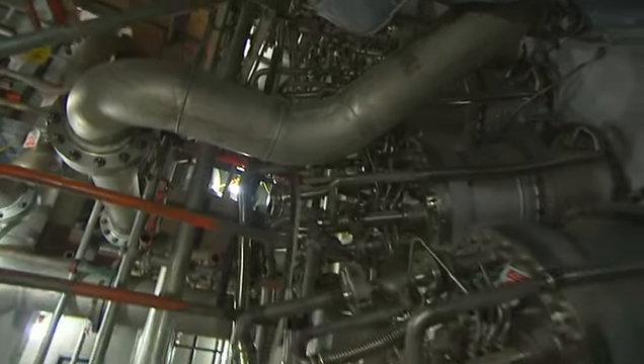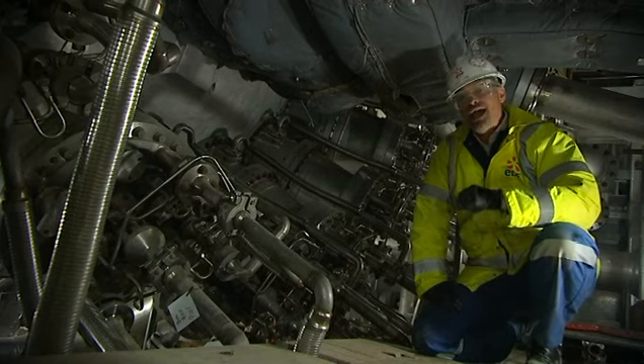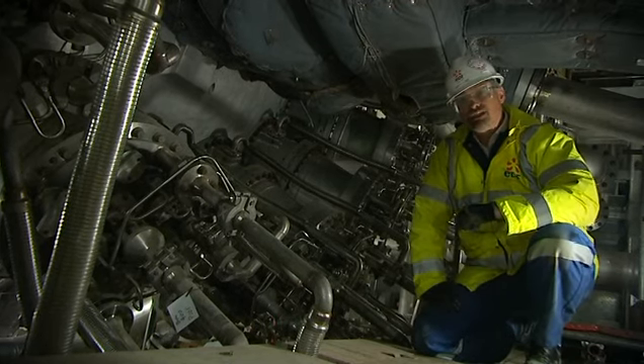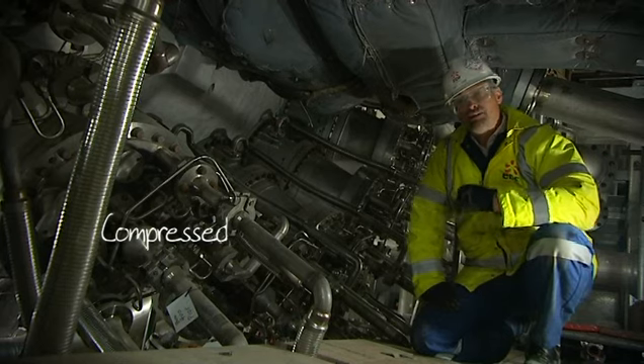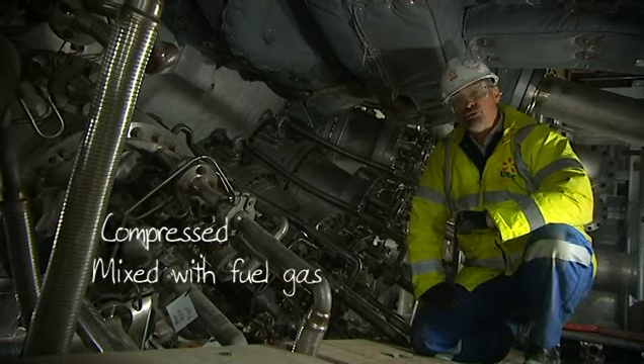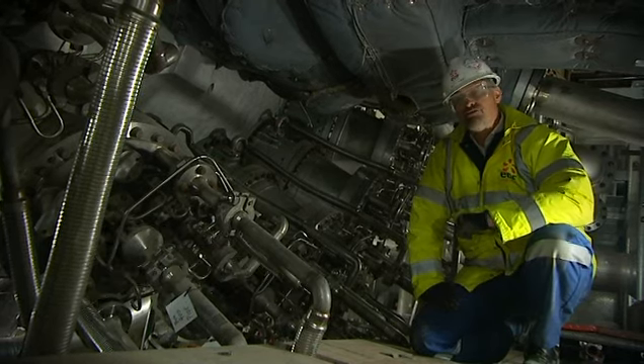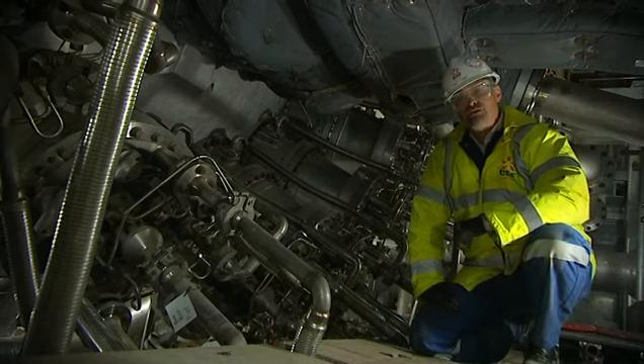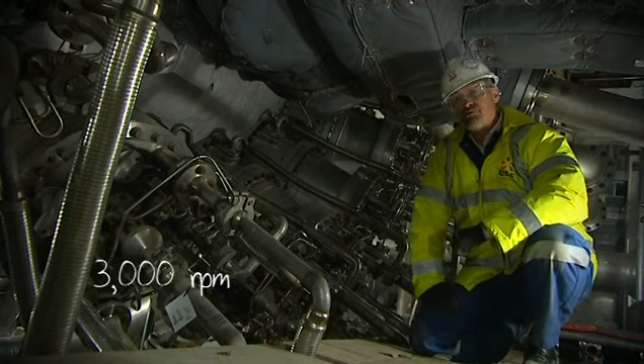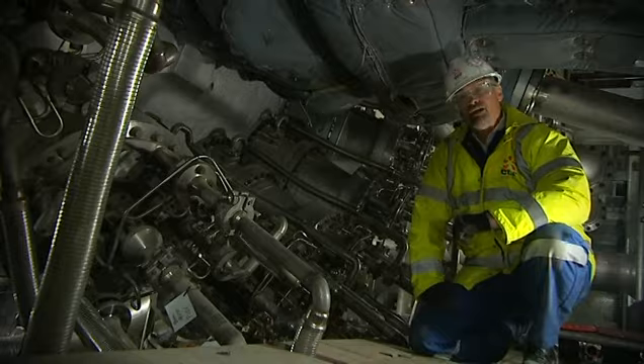Here we are in the heart of the power station, the gas turbine, which is essentially a jet engine on a massive scale. Air is drawn through the filter into the compressor, where it's compressed, mixed with the fuel gas and ignited to drive a power turbine. That power turbine operates at 3,000 revs per minute, turning the generator to produce 290 megawatts.